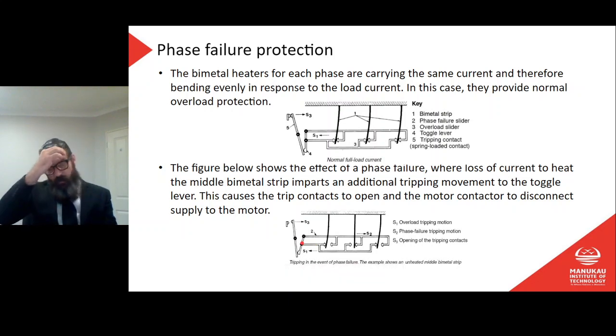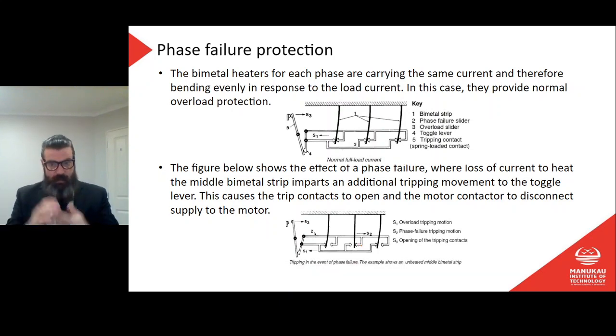If I lose one phase, so we've lost the middle phase in this example, not only will the two outer ones bend more to the left because they are getting a higher current, so they're going to bend more, the middle one now has no current, so it's going to start to bend back. So now they're working against each other, which will increase the likelihood of tripping. So that's how the bimetal, or the thermal overload, is able to protect the motor in the case of a phase failure.